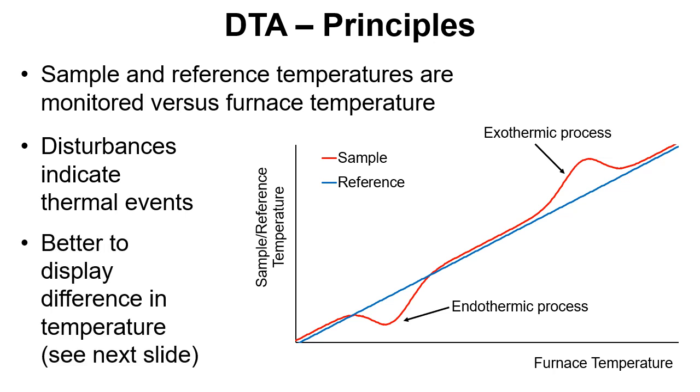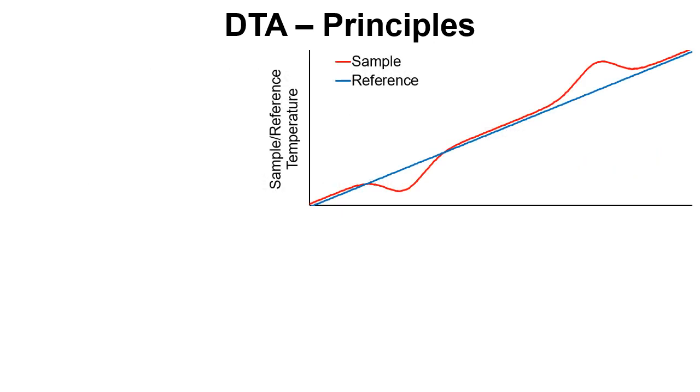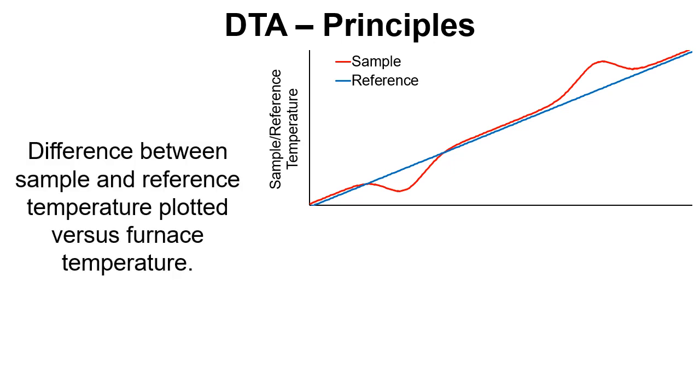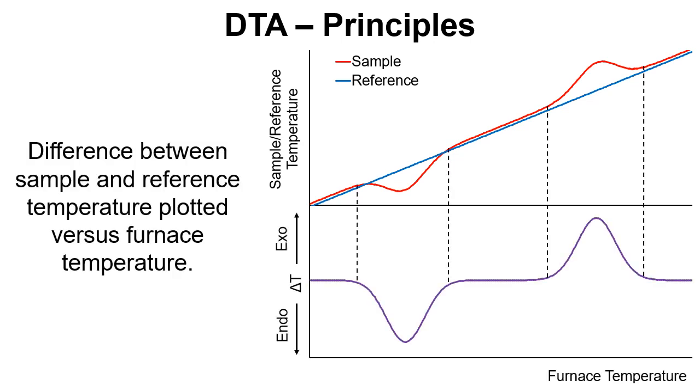Now it's better to display temperature difference versus furnace temperature. Here we have the thermogram temperature versus temperature plot and what we're going to do now is plot the difference in temperature. So it's the difference between the reference and the sample versus the furnace temperature.